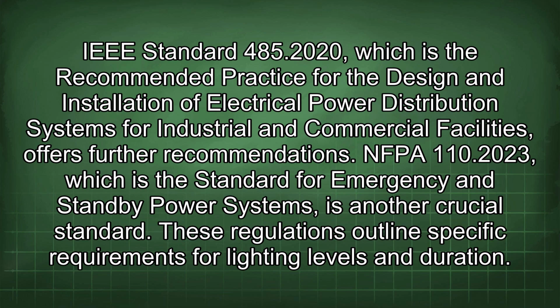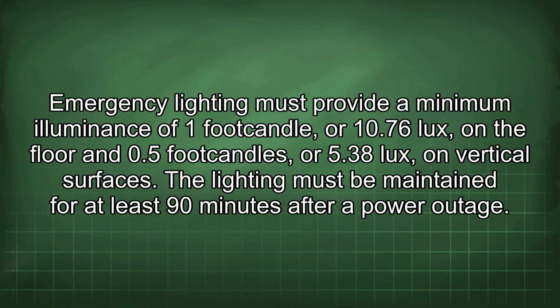These regulations outline specific requirements for lighting levels and duration. Emergency lighting must provide a minimum illuminance of 1 foot candle, or 10.76 lux, on the floor and 0.5 foot candles, or 5.38 lux, on vertical surfaces. The lighting must be maintained for at least 90 minutes after a power outage.